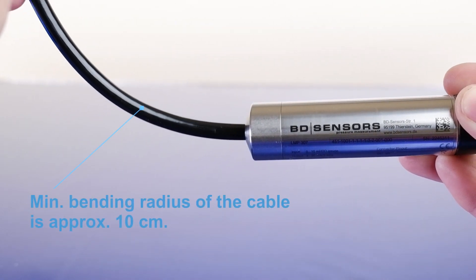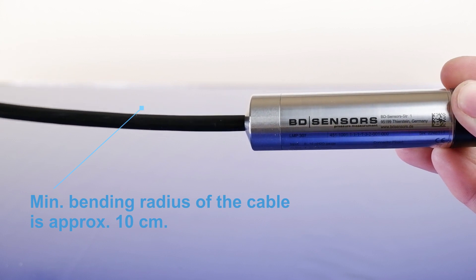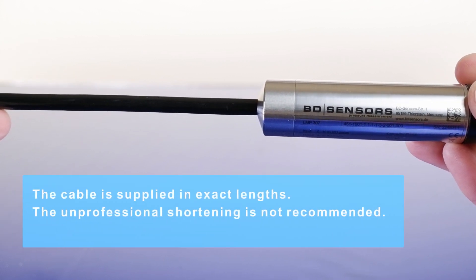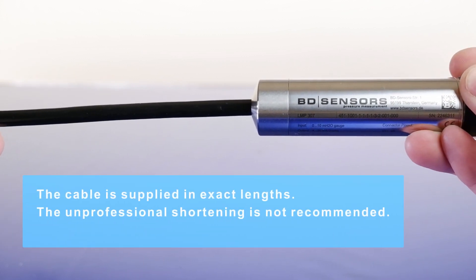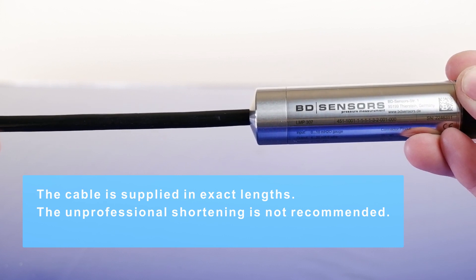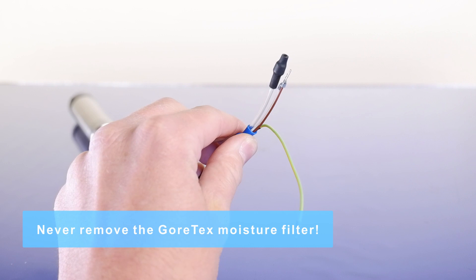Minimum bending radius of the cable is approximately 10 cm. The cable is supplied in exact length and unprofessional shortening is not recommended. Never remove the Gore-Tex moisture filter.